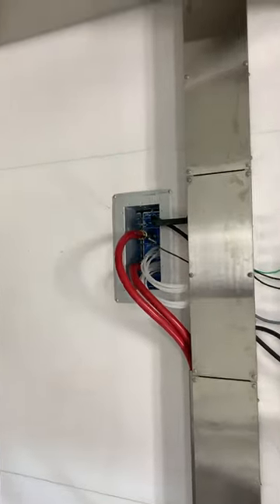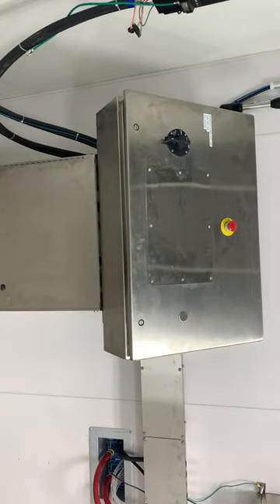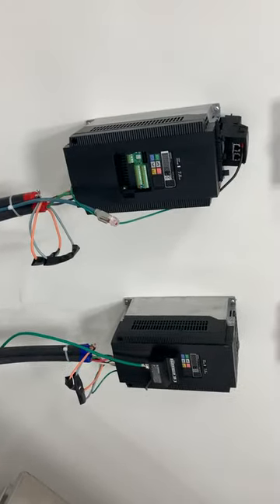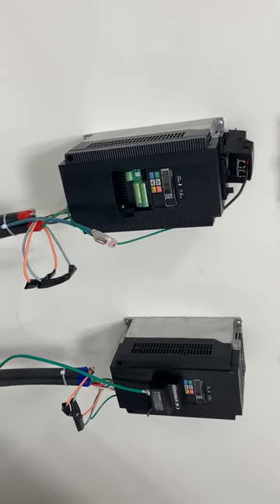This is the other side of the Tango — all the hoses are neatly run through this gantry to keep things clean and tidy. This is where the normal PLC would be located with a touchscreen, and you have the option to have a touchscreen in both places. VFDs control the pumps, so the compressors and recovery pumps can be controlled from zero to one hundred percent — you don't always have to run them at full capacity. There are two control panels in each room.